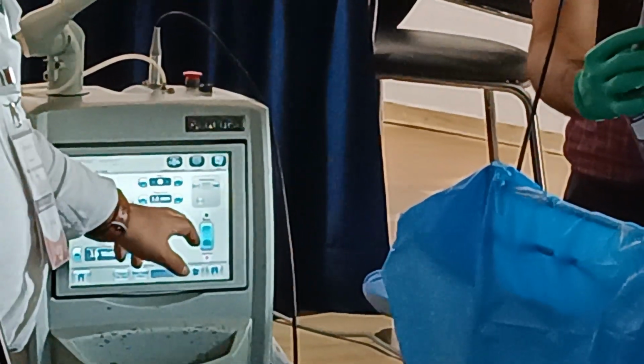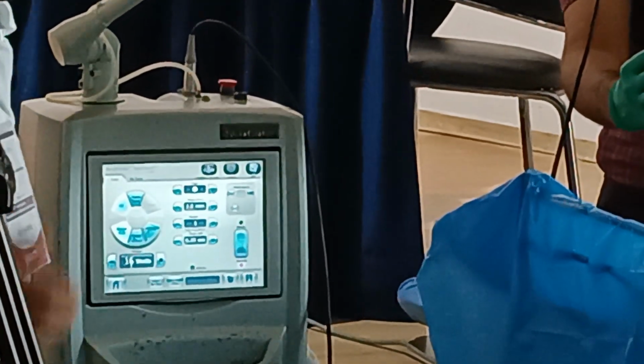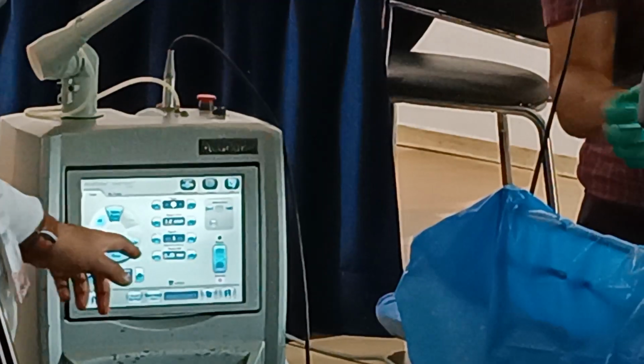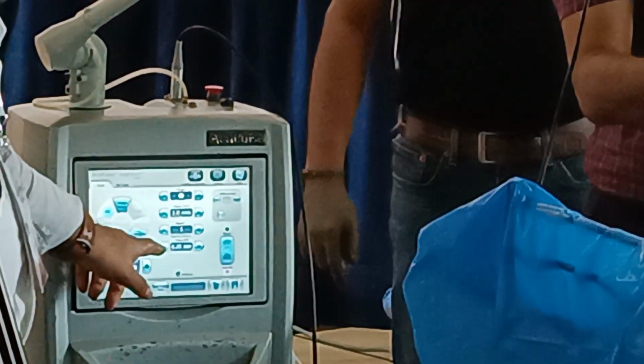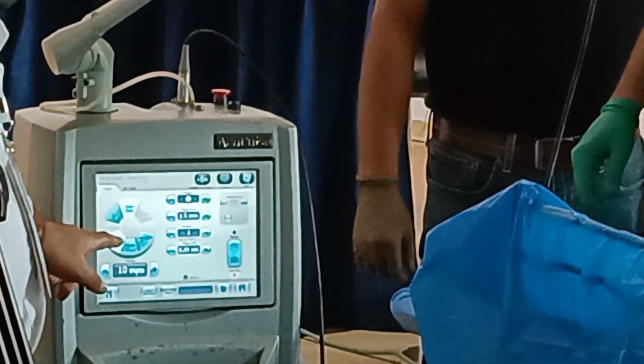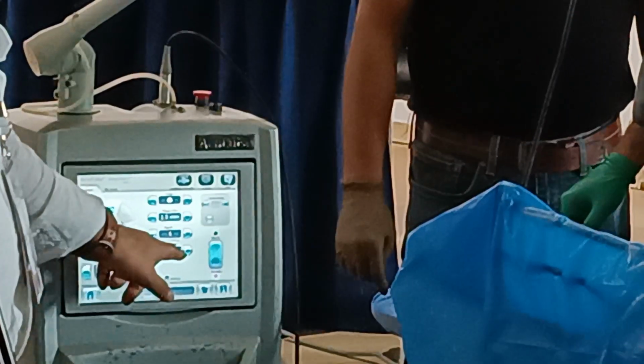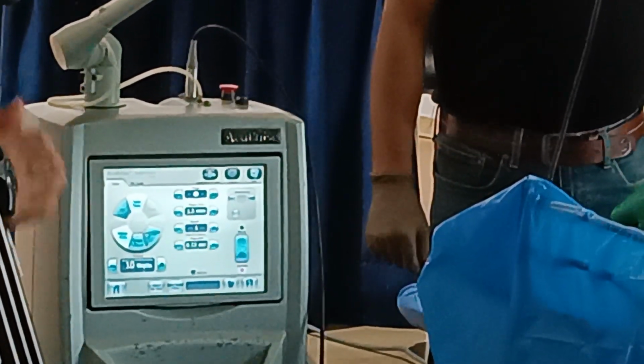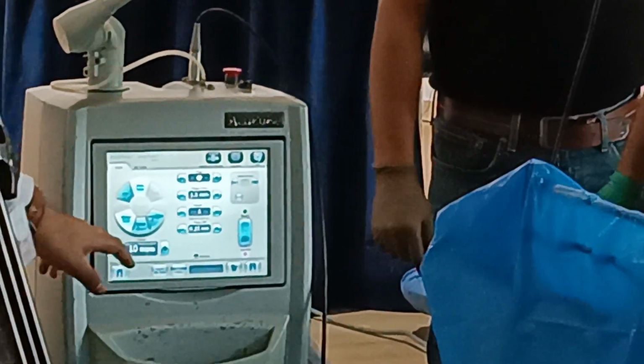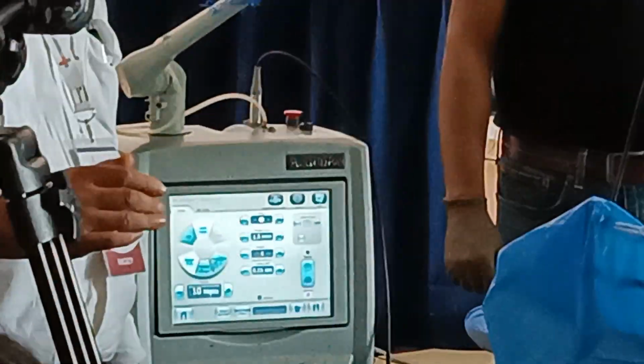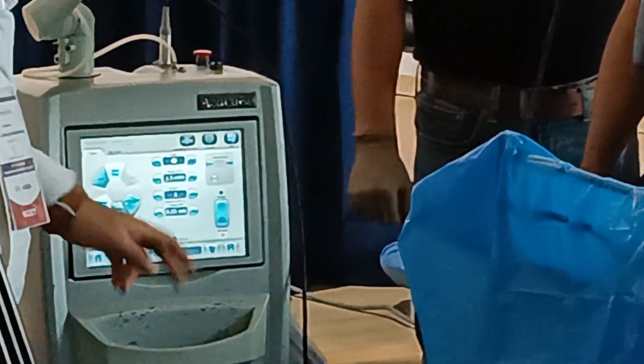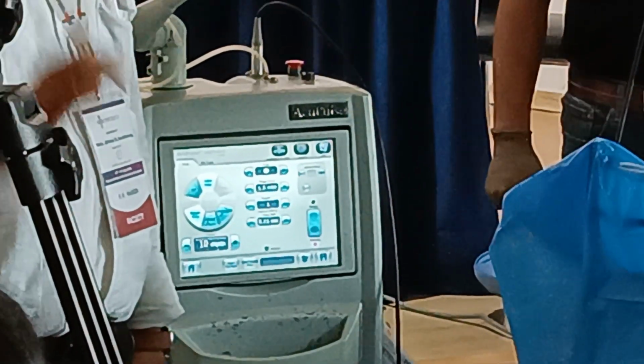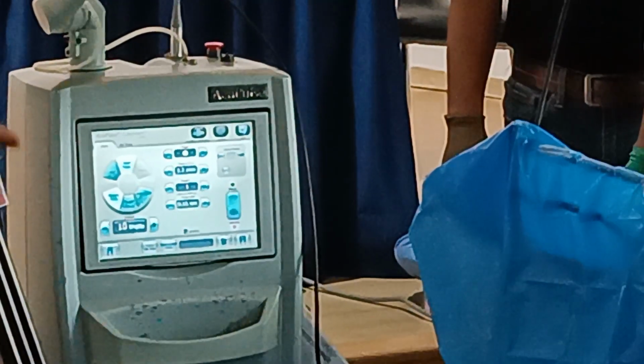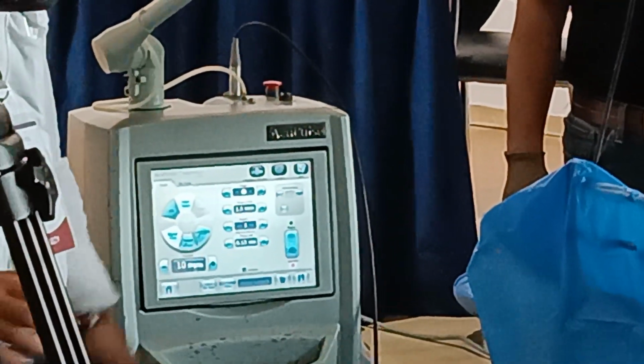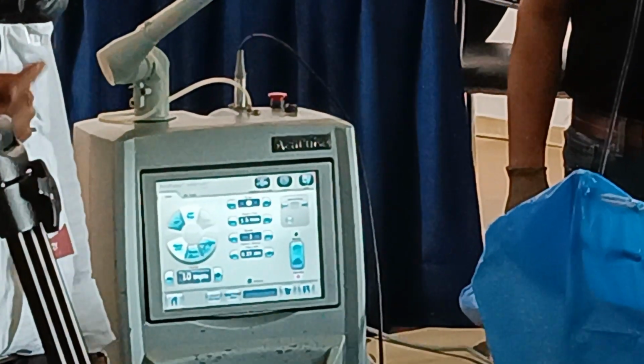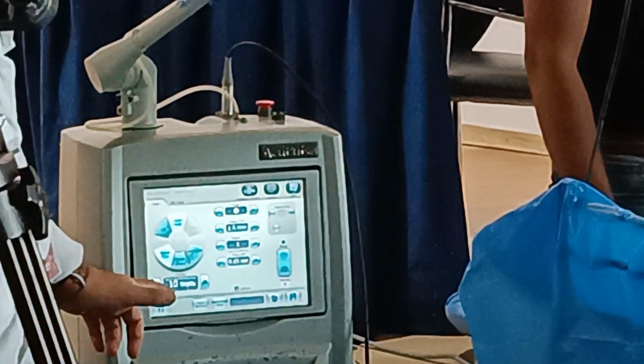Here is the depth. So, like we were discussing in the morning, in larynx, don't go very deep. You work layer by layer. Then this is the timer. Suppose I go into super pulse repeat mode, then this is the correct timer where you will get the appropriate energy delivery and good cutting beam. Wattage, normally for larynx, the indicated watts are 8 to 10 watts. If you are doing a stapedotomy, it is 21 watts, single shot. But here you work at 10 watts unless you want to do fulguration. Then you come to about 4 or 5 watts, which is just surface fulguration. Suppose you have oral cavity leukoplakia, erythroplakia, you just want to fulgurate with lower power.